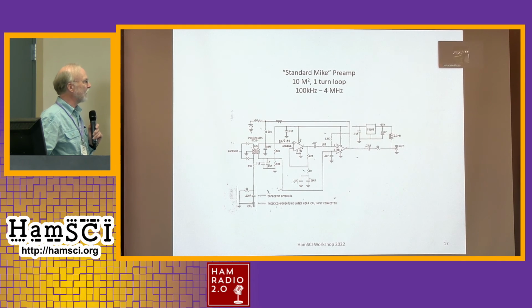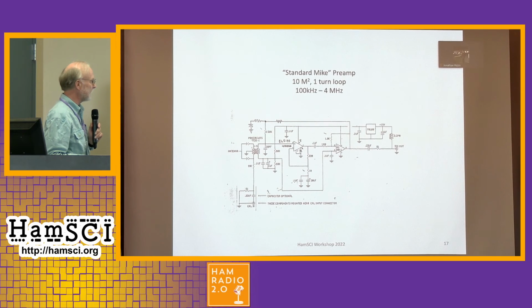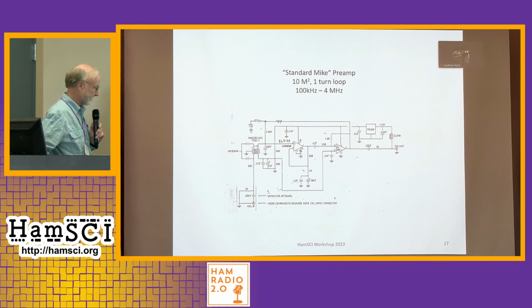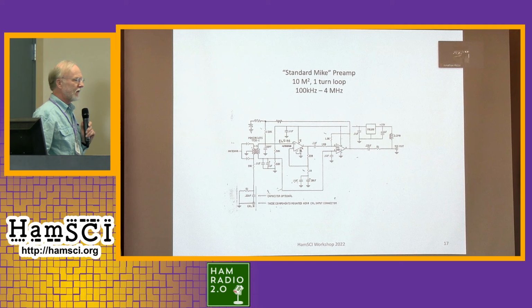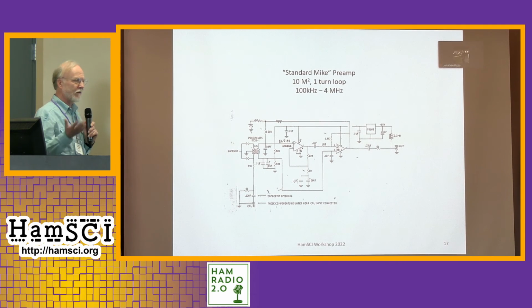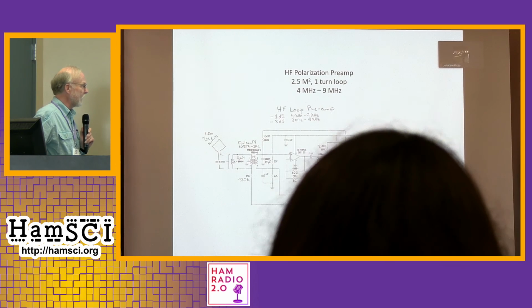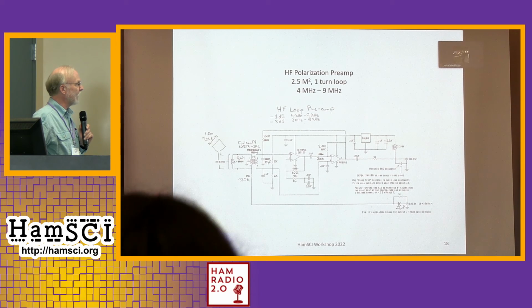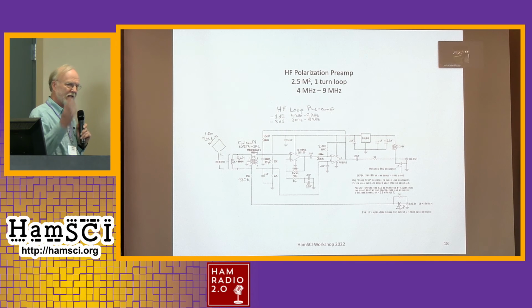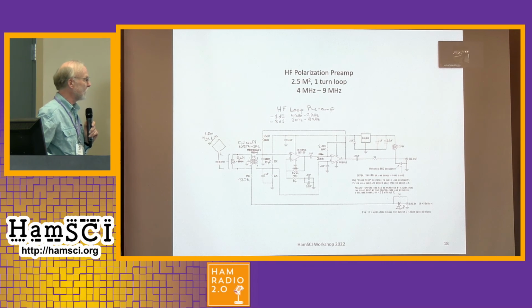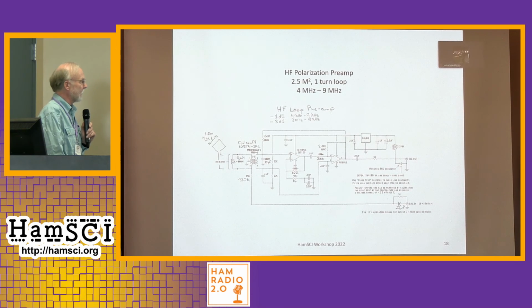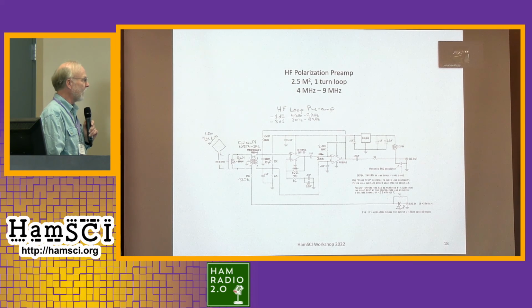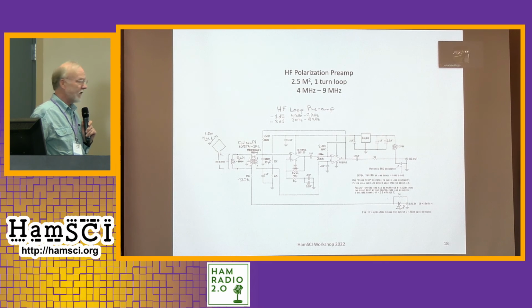Now, this is what I call the standard Mike preamp. This is what we mostly will use on our standard 10 square meter antennas. The intended response is 100 kilohertz to about 4 megahertz, and it gives about 500 voltage gain. And then this is the preamp that's been developed for the small loop, which gives a much wider range. We actually roll it off down at the low end because we're not interested in that. This was for the higher order aurora roars, the harmonics of the ion cyclotron frequency. So this gets up into the 9 megahertz range. And again, it gives probably about 500 gain. So very high gain, actually.